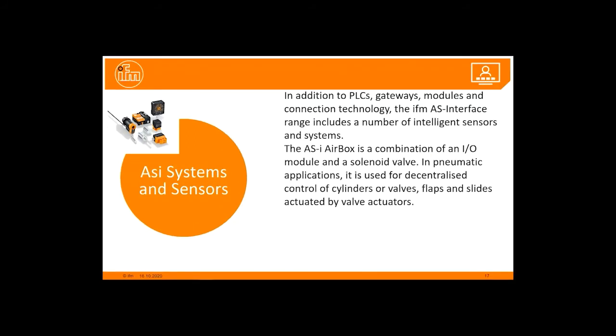ASI PC boards are offered for use in small housings, control cabinets and panels. The IFM product range features modules with digital and analog inputs and outputs, just as an example. In addition to PLCs, gateways, modules, and connection technology, the IFM ASI range includes a number of intelligent sensors and systems, typically like the ASI airbox. It's a combination of input and output module and a solenoid valve. In pneumatic applications, it is used for decentralizing control of cylinders, valves, flaps, slides actuated by valve actuators.